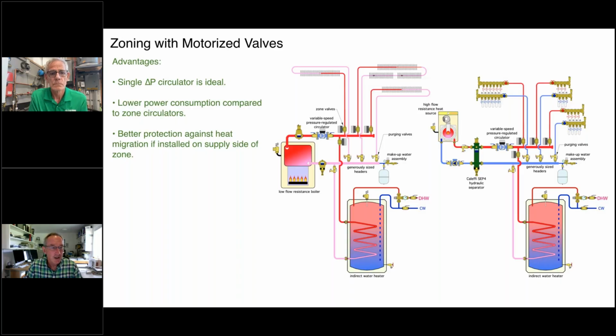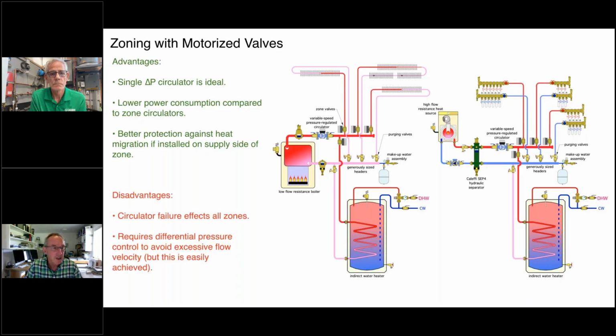Advantages, disadvantages. A single delta P variable speed circulator is ideal. That's what we've shown over here. These are widely available today from just about any company that is selling circulators for hydronics. Lower power consumption compared to zone circulators. idronics 36 will give you some specific numbers where we compare a wattage input to the distribution system for zone circulators versus that for zone valves. And because it's a valve that fully closes when it's off, it basically prevents heat migration.